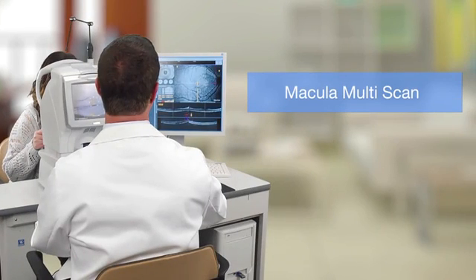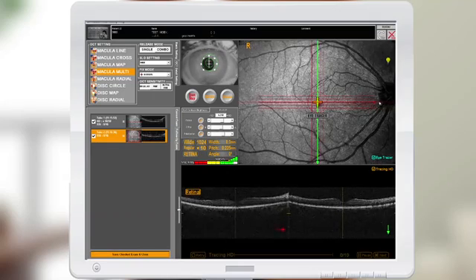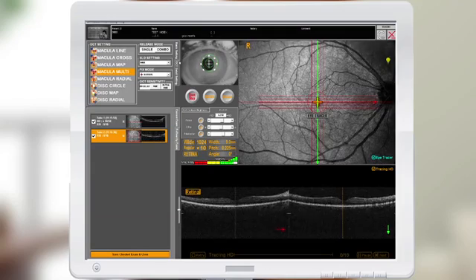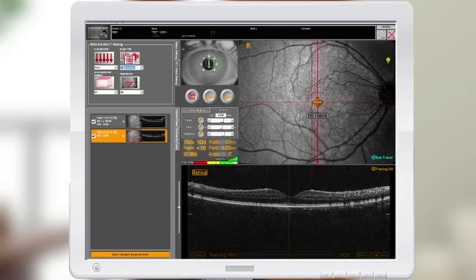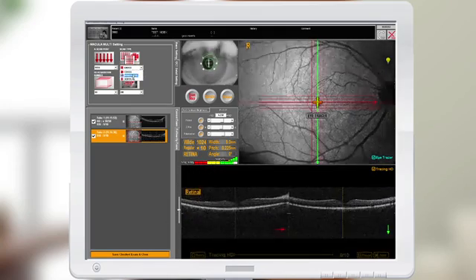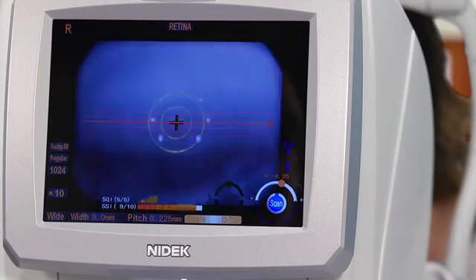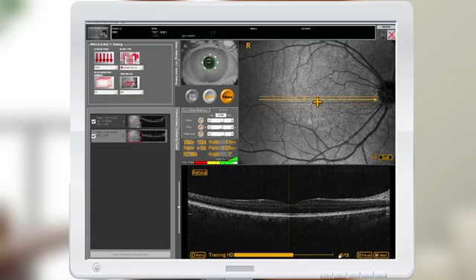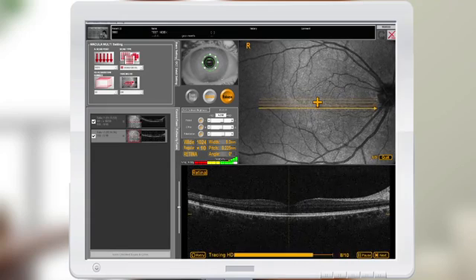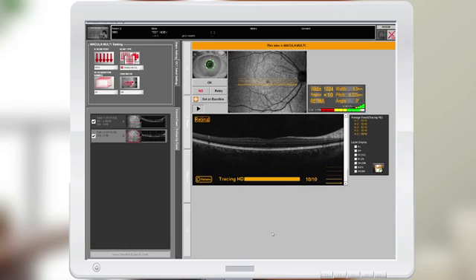The next scan pattern I will demonstrate is the macula multi. The macula multi defaults at a cross; however, it can be programmed to default as a horizontal scan, a vertical scan, or back to a cross. I'm going to demonstrate the horizontal scan. Align the B-scan and pupil image until you get a good signal strength index, then press the button on the joystick. As you can see, we're averaging 10 per line. This can be adjusted from 1 up to 120 if you desire a more high-definition scan.